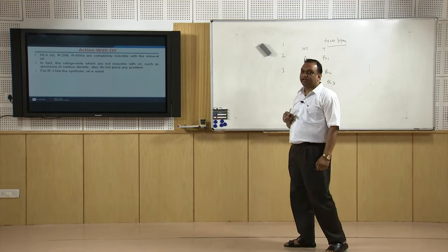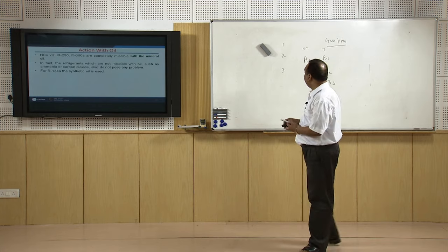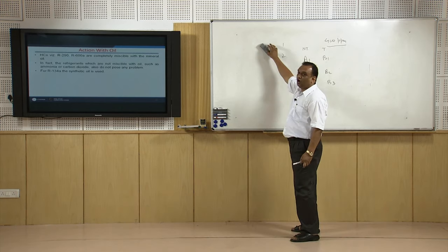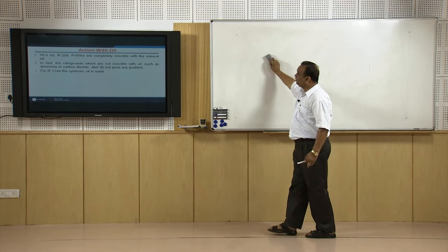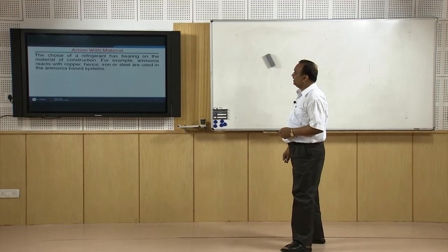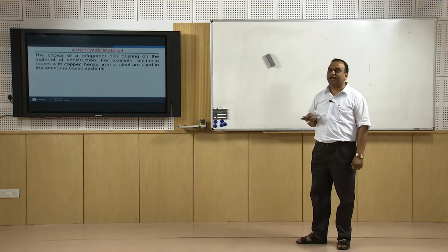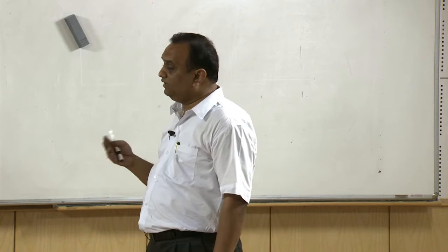Now, action with the oil: the refrigerant should not react with the oil. Some of the refrigerants which are hydrocarbons are completely miscible with the oils. Ammonia is not miscible with the oil, that is the issue with ammonia. R134a is not miscible with mineral oil, natural mineral oil, so synthetic oil is used in the case of R134a.